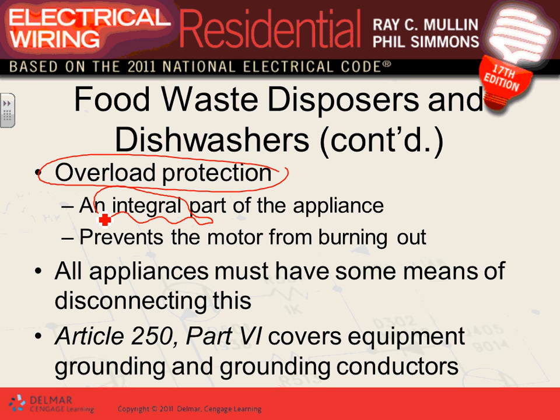Built into the appliances. So we talked about this one. All of them require disconnect means. Appliance is very, very important. This requires disconnect means. Why? You stick your finger in the garbage disposal, you want to bring it back with you when you move your hand, right? That's it. That's really what the disconnect is. You physically, mechanically isolate the equipment from the power that powers it. So no accidental connection, energizing of the equipment.